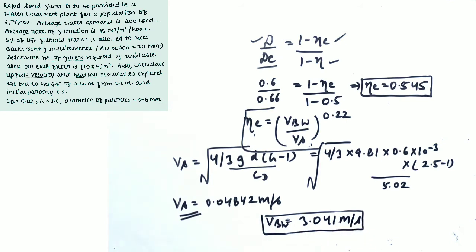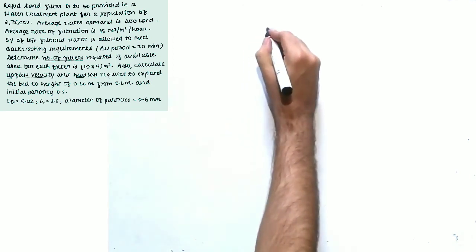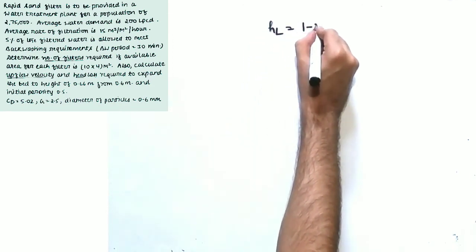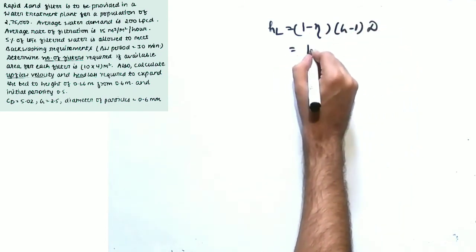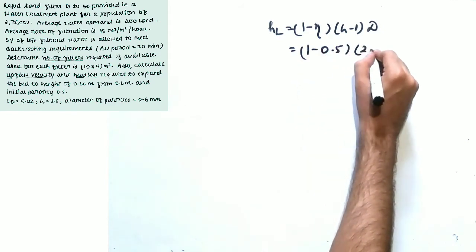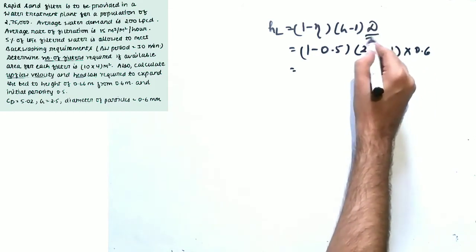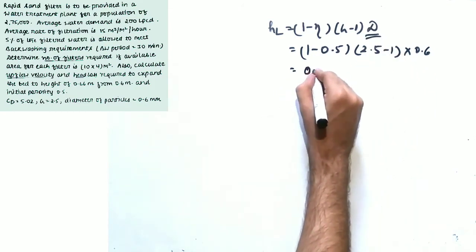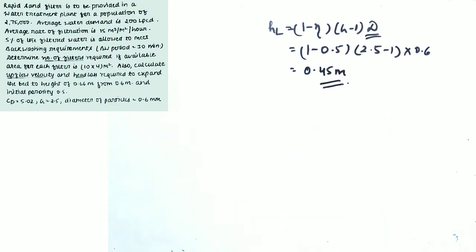The examiner can confuse you by asking for the upflow velocity rather than the backwashing velocity — but they are the same. For head loss, the formula is: H_L = (1 − η) × (G − 1) × d. Substituting: (1 − 0.5) × (2.5 − 1) × 0.6 = 0.45 meters. The units are the same as d (meters). So H_L = 0.45 m. This was the last part asked in the question.